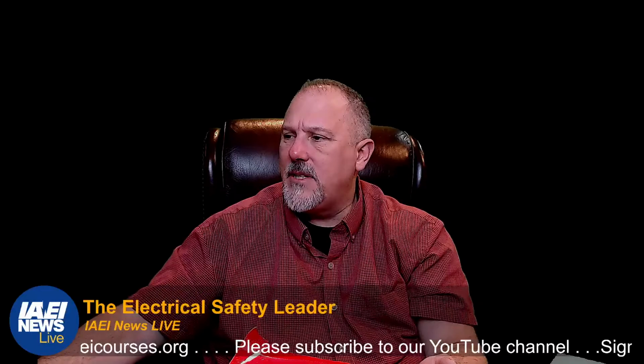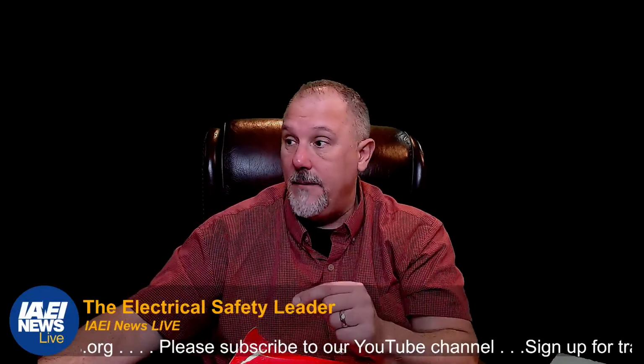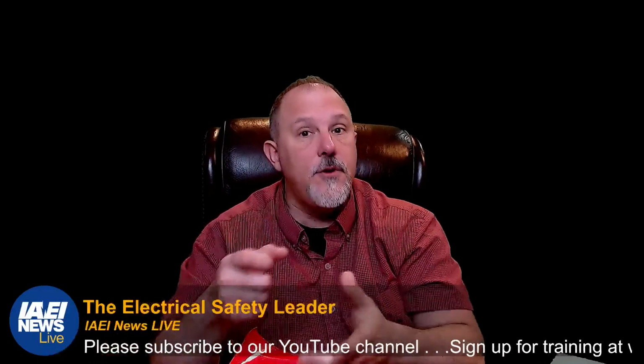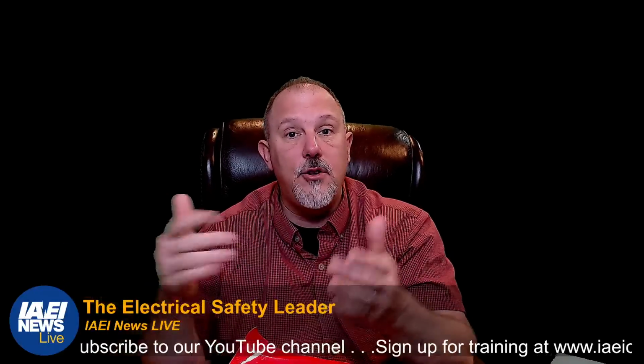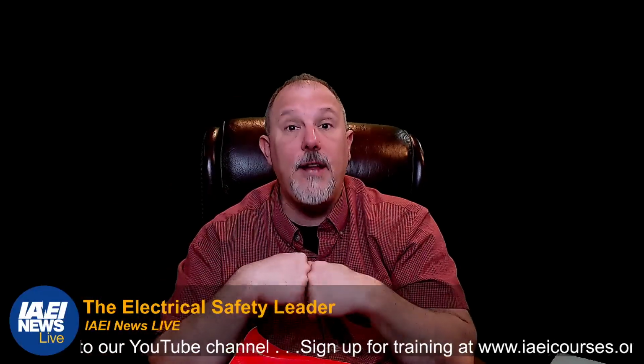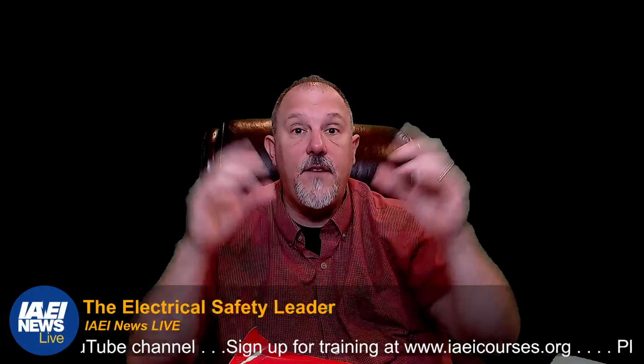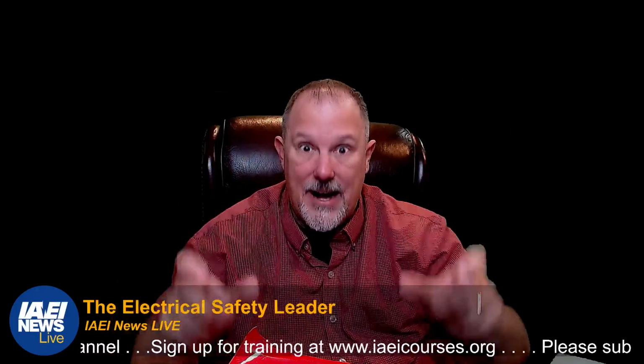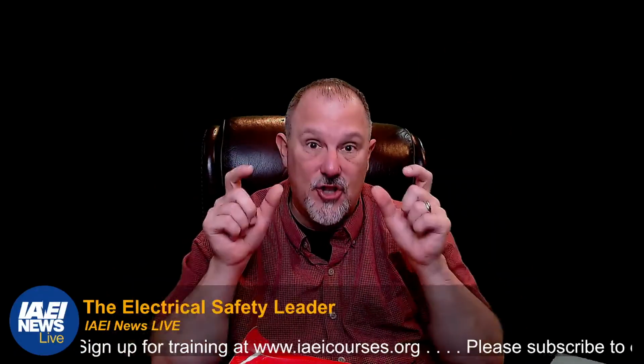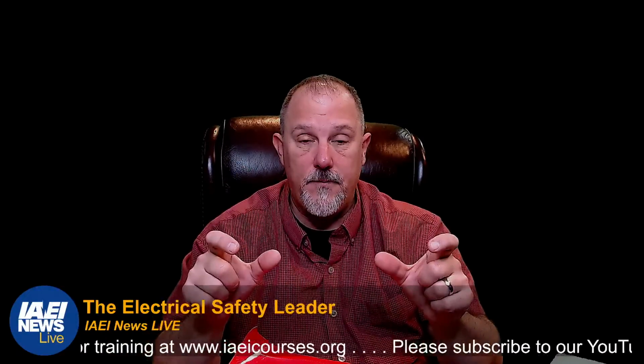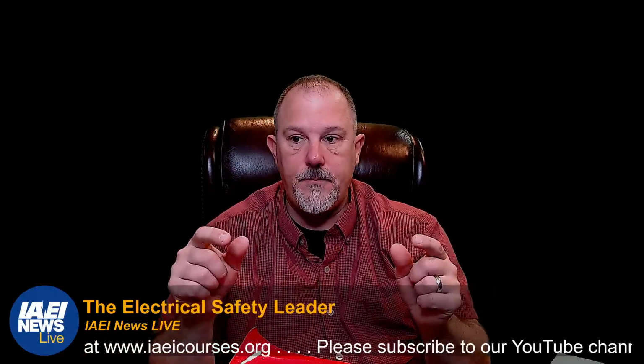The only thing I'd say you would absolutely need energized for is if you're going to do thermography, which you have to do annually. So you're going to have to take the dead front off annually. If you don't have those little IR windows in there, you could put IR windows in the trough of a panel board. They make them, they're out there.